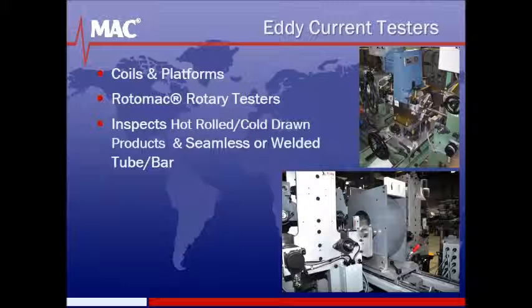MAC's eddy current inspection systems incorporate computer-based test instruments and test coils. MAC uses 2 general types of eddy current test coil technologies, encircling or sector coils and spinning or rotating probe coils. Installation can be in-line or at a separate test station. End suppression circuitry, when combined with an optional sensor, can be used for testing cut lengths to prevent false signals from leading and trailing ends.